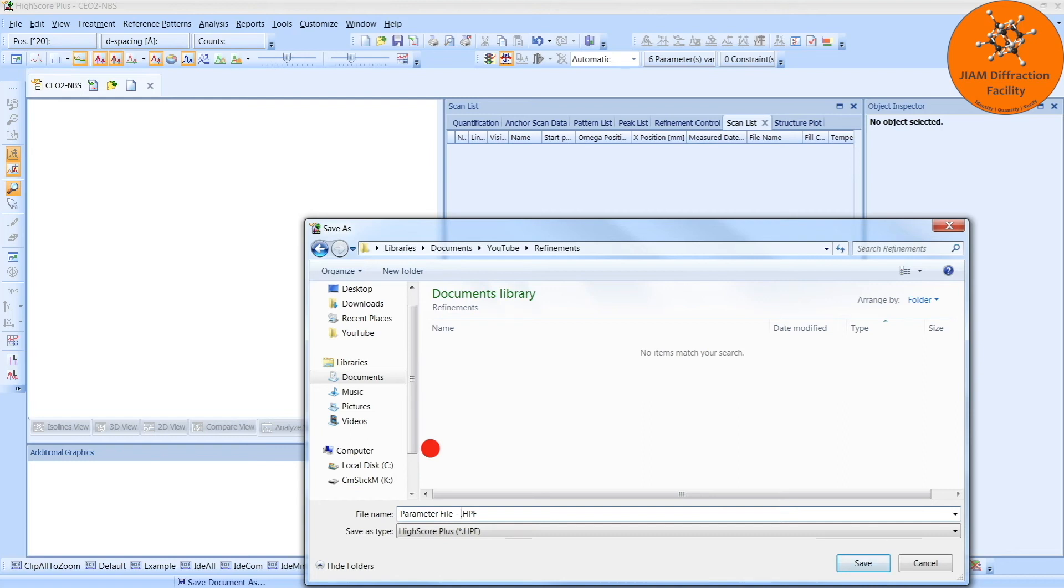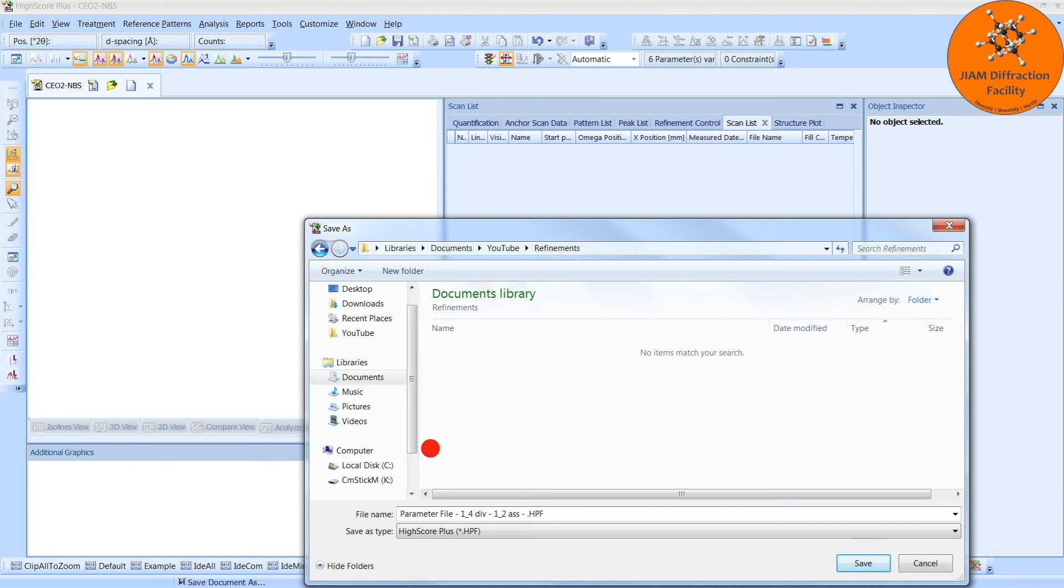And I will save this as something like parameter file, and then normally I would save it with the optics that I use. For instance, one-fourth divergence slit, one-half anti-scatter slit, and then I would just list the rest of the optics.